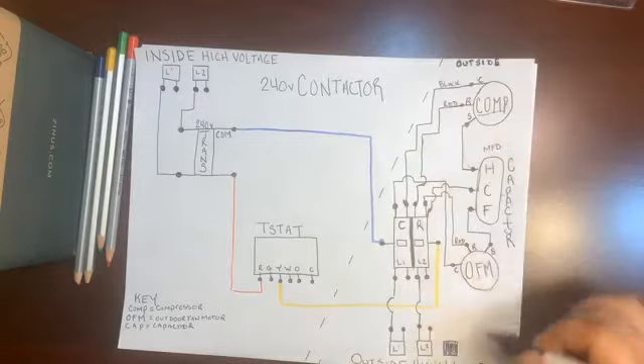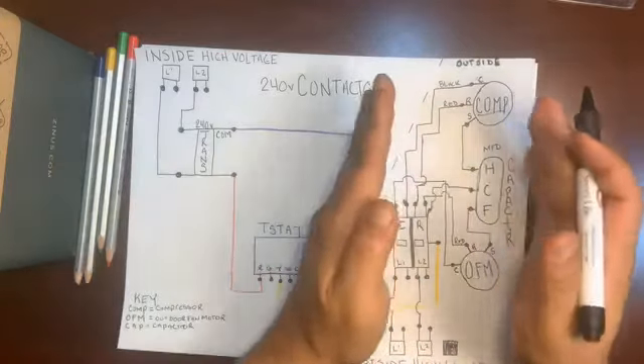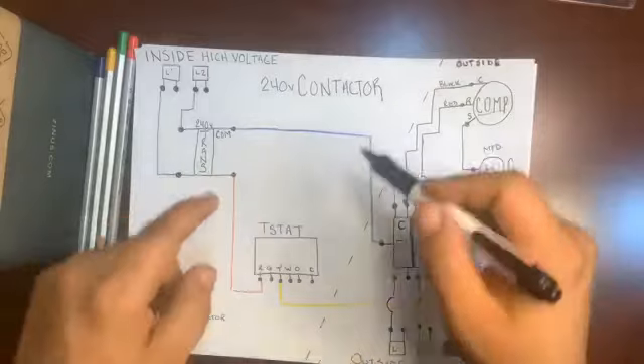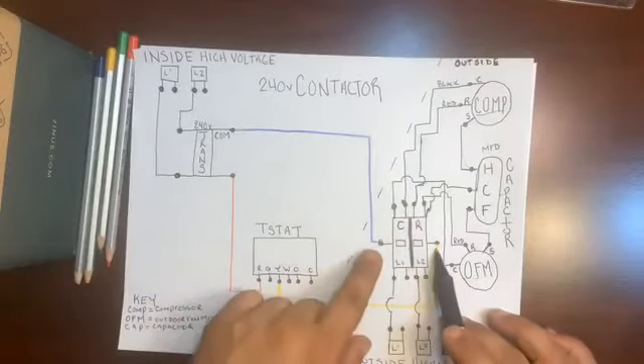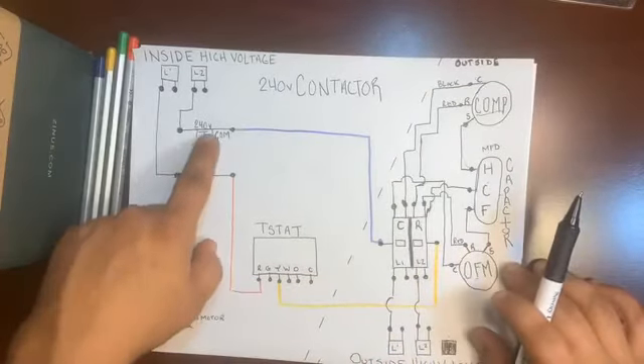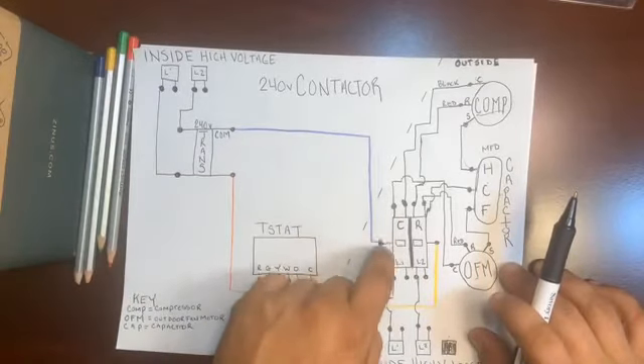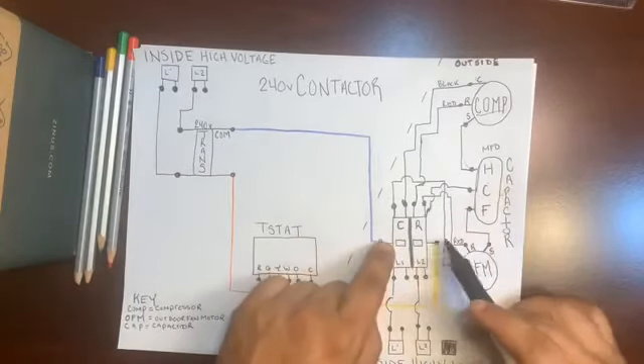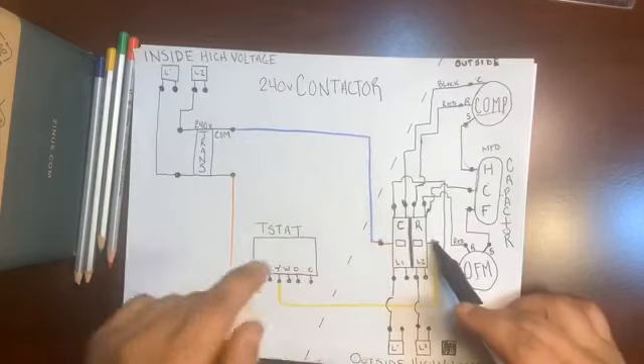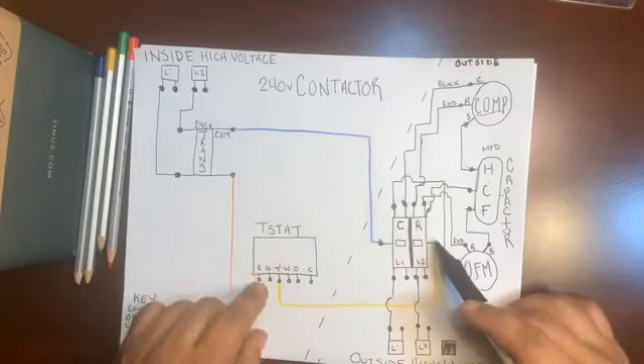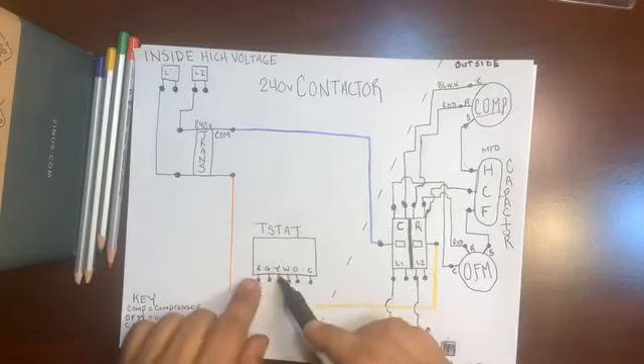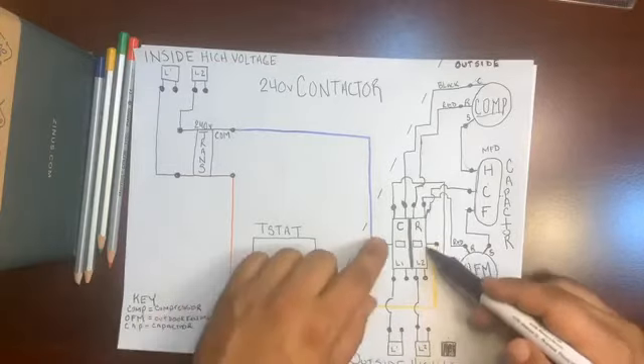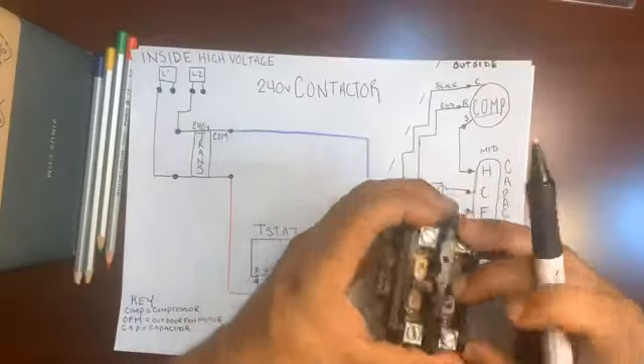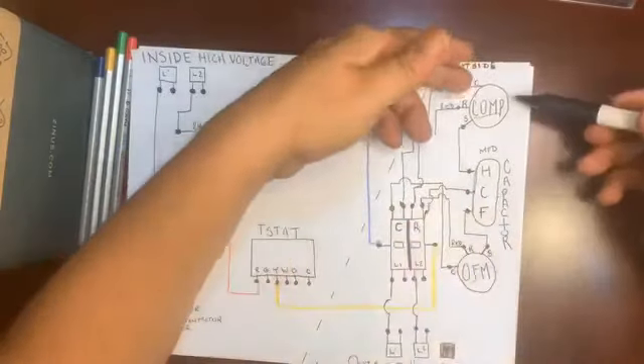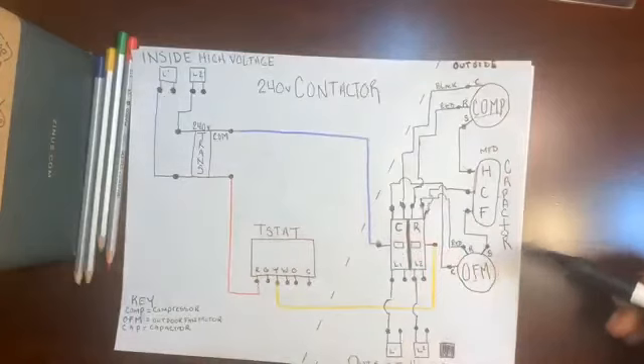We will go deeper into this. The whole point of this is to tie in, again, let's keep it back to the contactor and the low voltage relay. This transformer is consistently sending its 24-volt common, keeping this side charged. This relay won't engage unless it gets its 24. Thermostat says, Mr. Homeowner's hot, turn on the cooling. 24 volts is jumped through the red into the yellow. It travels, closes this contactor down. It closes these poles down, completes the circuit, and now the compressor and the outdoor fan motor turn on.